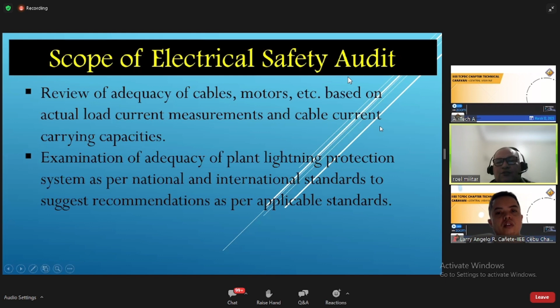Examination of the adequacy of plant lightning protection systems as per national and international standards, to suggest recommendations as per applicable standards. It's more about the lightning protections. It will review the hazardous area classification carried out in the plant, and review the selection and installation of special electrical equipment to suggest recommendations as per applicable standards. It will review also the electrical preventive maintenance program in the plant, and examine the documentation, checklists, work permits, test records, etc., and suggest recommendations as per applicable standards.